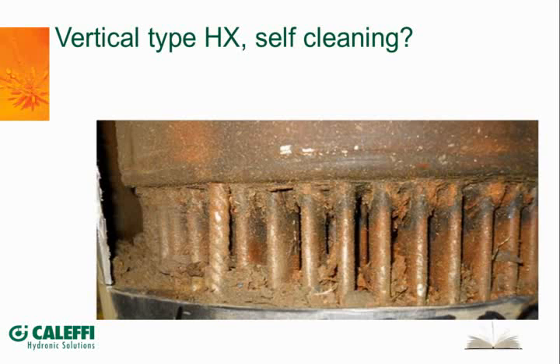I looked at this one and thought, whatever they were circulating in this radiation system must have been nasty, dirty water, or there was a leak somewhere in the system being made up continuously. This is time-accumulated rusty mineral scale, telling me there are other ferrous metals in the system going bad, along with hard water that isn't getting flushed out and cleaned.